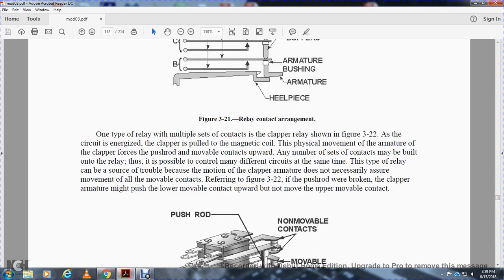One type of relay with multiple sets of contacts is the clapper relay shown in figure 3-22. When the circuit is energized, the clapper is pulled by the magnetic coil, and the physical movement of the armature of the clapper forces the push rod and movable contacts upward. Any number of sets of contacts may be built onto the relay. Thus, it is possible to control many different circuits at the same time.